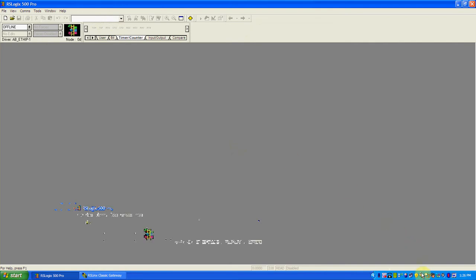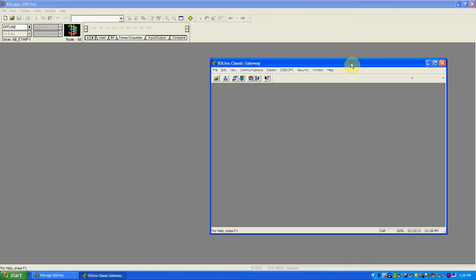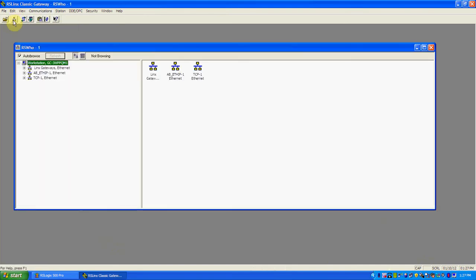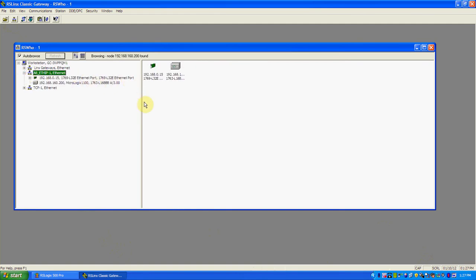The other thing I said I'd show you is, down here, there's something called RSLinx. This is an all new piece of software to you. It's running in the background whenever you have RSLogix 500 open — this software is designed to communicate between Rockwell products. In here I can set up all my different drivers, I can do this RS Who, and it shows me everything on the network and how it's communicating and how it's set up. I can change settings, change IP addresses. When you say download, it's this software that's handling the downloads and the uploads — it does all the communications in the background so you don't really see it. This is the screen that comes up when you go Comms, System Comms. We'll talk about this software in more detail as we move through the course.